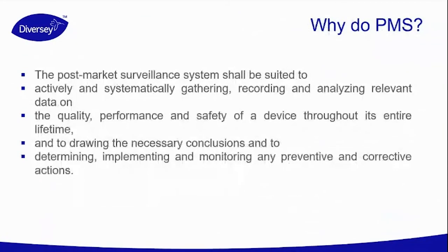But why do the PMS? The post-market surveillance system should be suited to actively and systematically gathering, recording, and analyzing relevant data on the quality, performance, and safety of the medical device throughout its entire lifetime, and to drawing the necessary conclusions to determine, implement, and monitor any preventive or corrective action that will be needed.